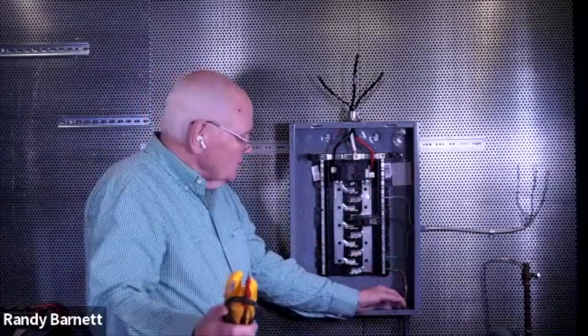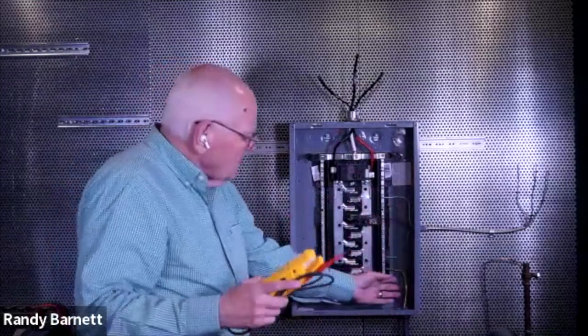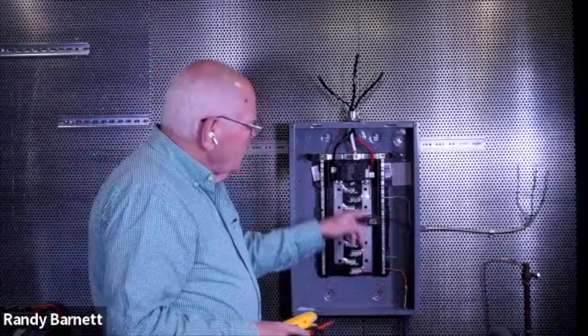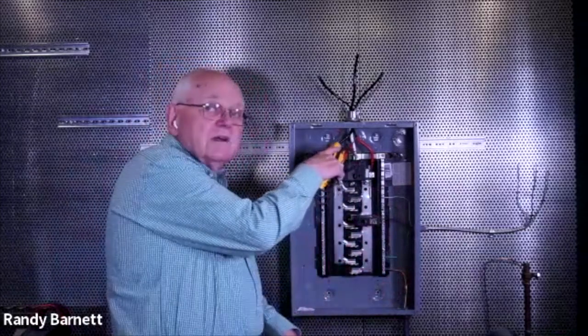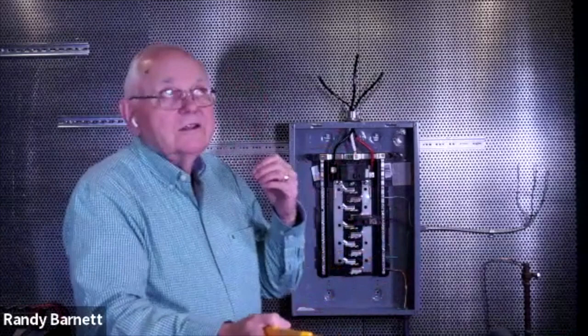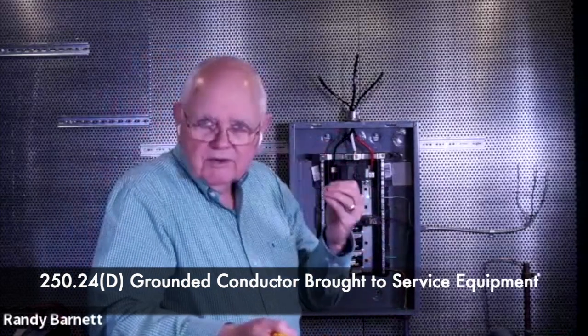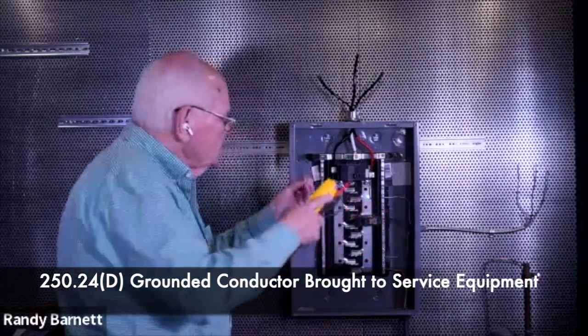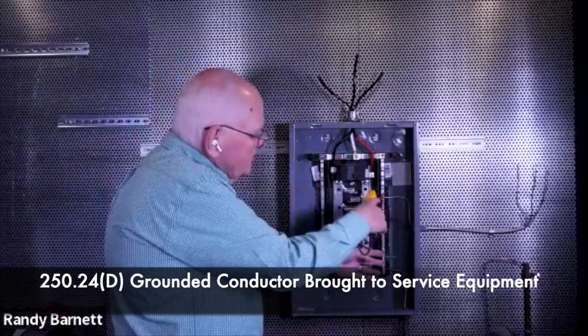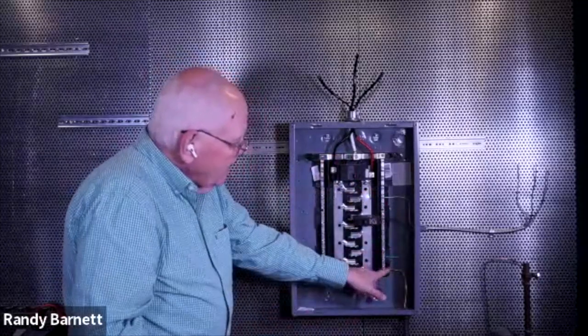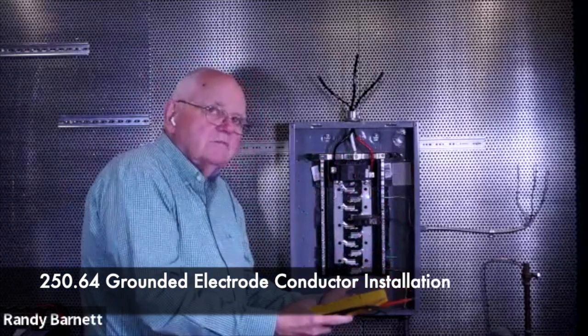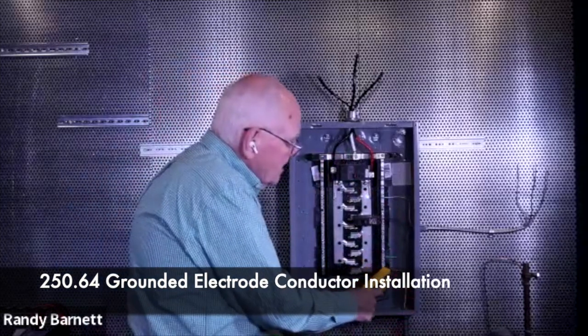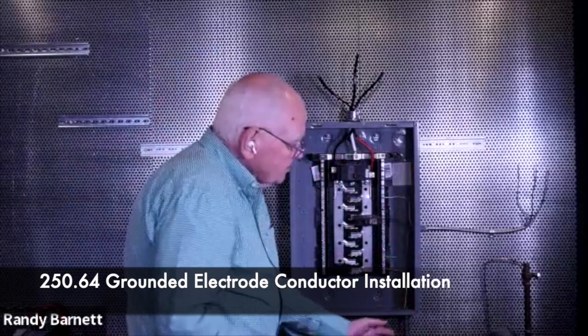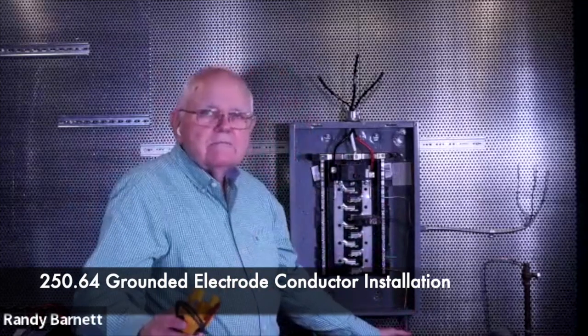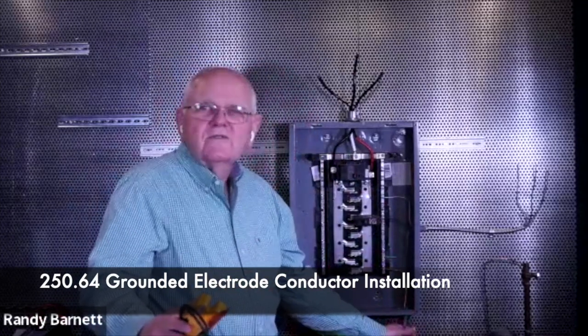One of the requirements for our service is the first disconnecting means of the meter, but I'm going to go ahead and connect the neutral from the service. And by the way, that neutral, even if I'm not going to use it for some reason, I still have to bring it in from the service. So I bring this neutral in, connect it to the grounded bus bar, and now I take this bare copper wire, it happens to be bare, and I take this bare copper wire off, and it runs out. Actually, I've got it running through some EMT. All we have to do is give it some physical protection.